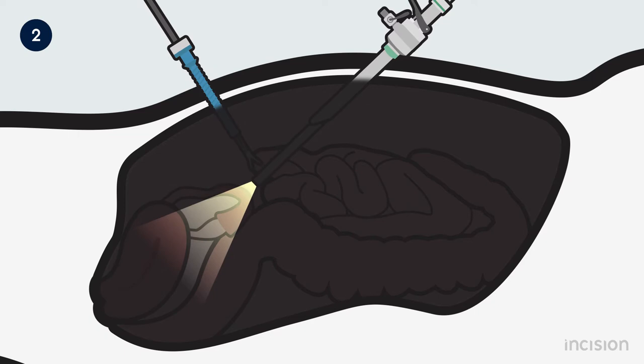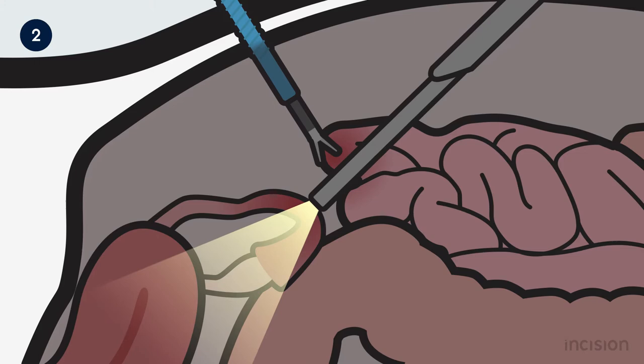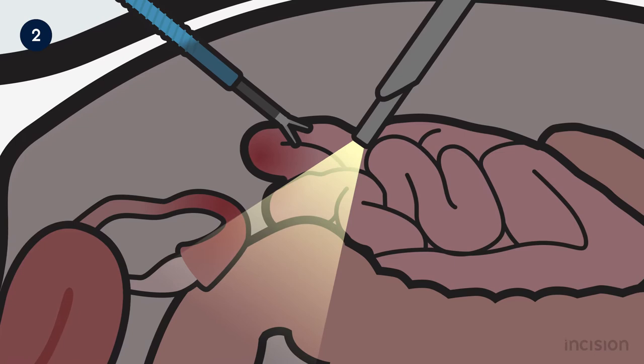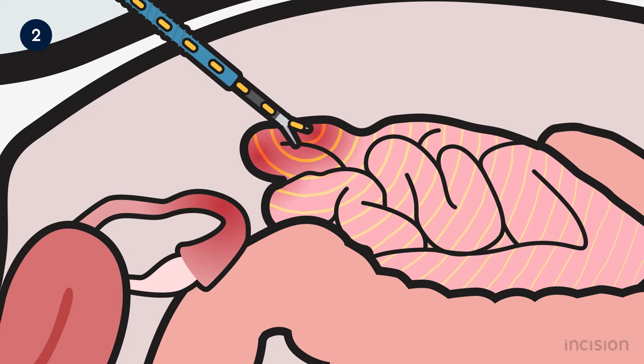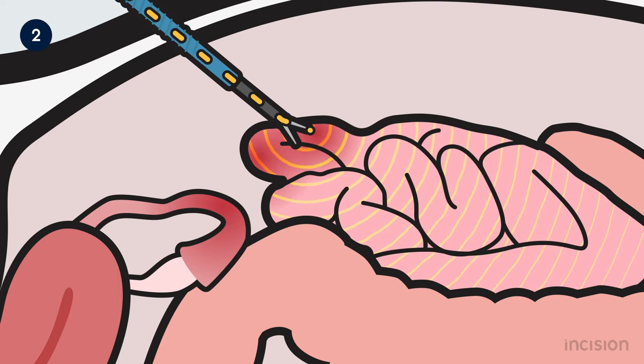Both factors increase the chance of accidental contact between the electrode tip and unintended tissue. If unintended tissue is in contact with or near to an activated electrode tip, it has a large chance of being negatively affected by current going through this pathway. This can result in the burning or perforation of structures, which may result in bleeding, spillage of bodily fluids, or the ignition of bowel gases.